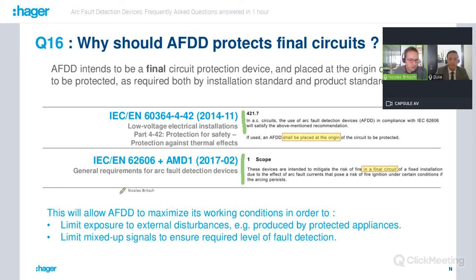Actually, this is for two reasons. This allows the AFDD to maximize its working conditions in order to limit the exposure to external disturbances, for example those produced by the protected appliances of the circuit, and also to limit mixed-up signals to ensure the required level of protection. So it's both in order to be sure that we have good protection and also to limit the probability of disturbances and, for example, unwanted tripping. Okay, it's a very clear objective and it's very typical for arc fault detection device. Thank you, Nicolas.